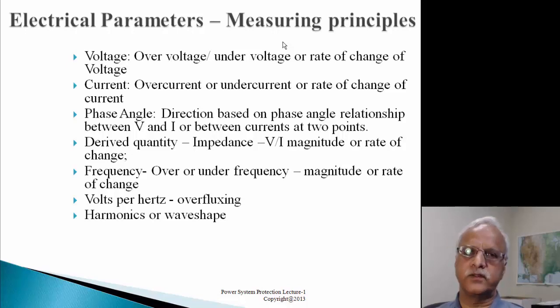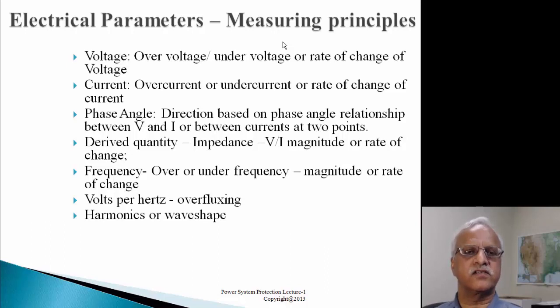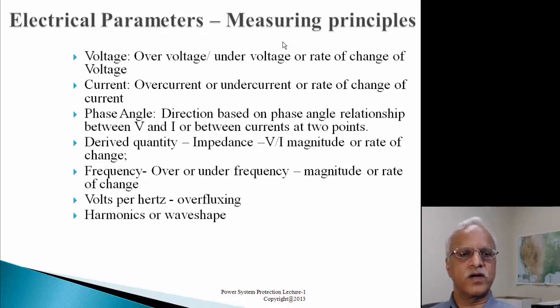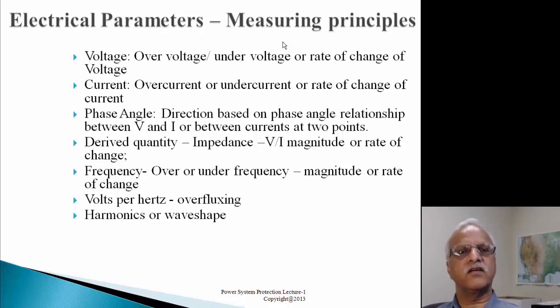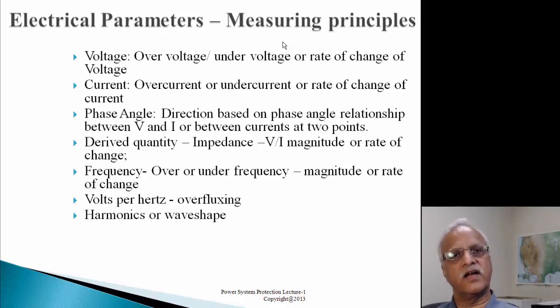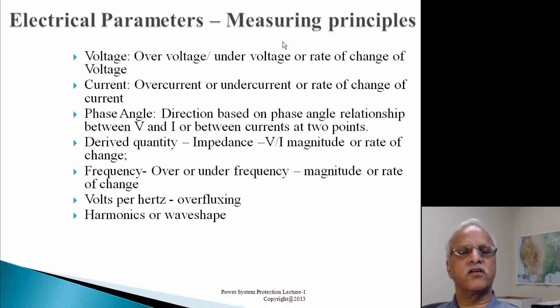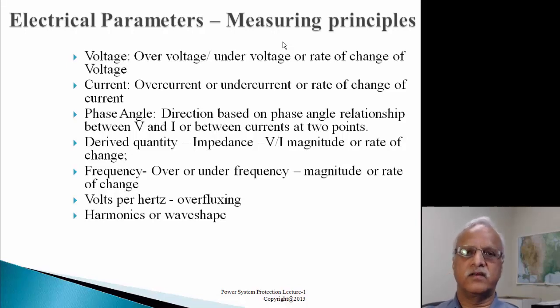Volts per hertz is another parameter used for protecting transformers, where the voltage-to-frequency ratio is always constant - it equals k times the flux density in the transformer. If that ratio increases, flux density increases, causing the transformer core to saturate and resulting in overheating. We also use the harmonic content in the sinusoidal current waveform to determine whether we are energizing a transformer - where we see 8 to 16 times rated current as inrush current - versus an actual fault. We look at the harmonic content to make this decision.